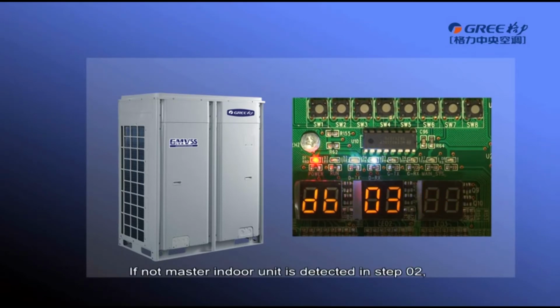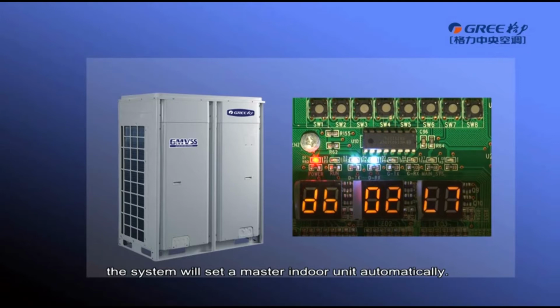If no master indoor unit is detected in step 02, LED 3 will display error code L7. In this case, all outdoor unit buttons are temporarily not functioning. Users can set the master indoor unit through the debugging software, wired controller, or remote controller within 1 minute. If no master indoor unit is set within 1 minute, the system will set a master indoor unit automatically. Then the system enters the next step automatically.